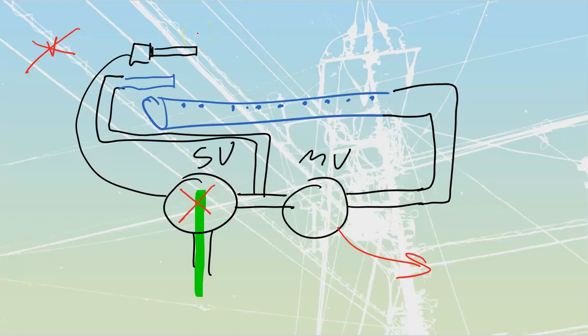Let's talk about maintaining these ones. For a pilot light, there are a couple of things that cause these to go out. One of them is that orifice, the small tiny hole on the end of your pilot flame gas supply, which can get ashed over. Small amounts of ash build up from natural gas. All you need to do is clean that thing off. Don't scrub it with a metal brush or anything like that, just give it a quick little wipe and a blow. Don't press down, because you don't want to shove stuff inside of it either, just a light little wipe to take everything off of that one.